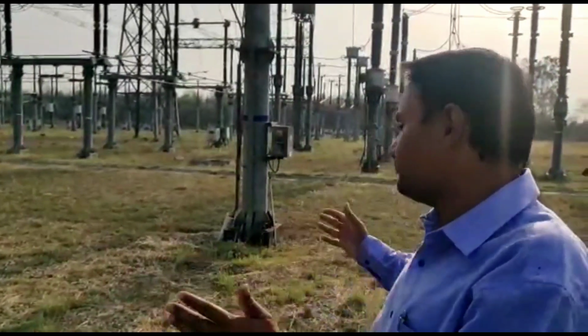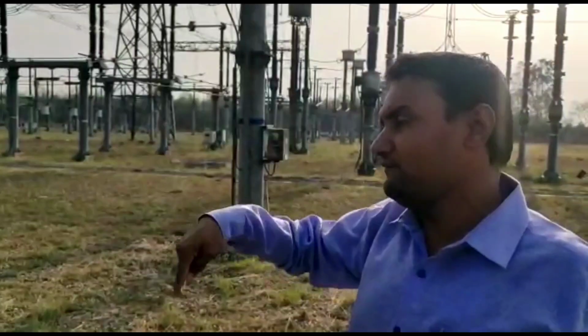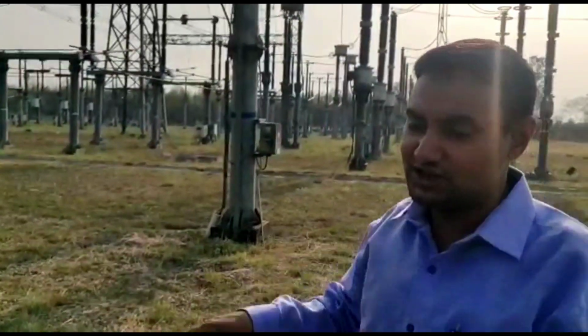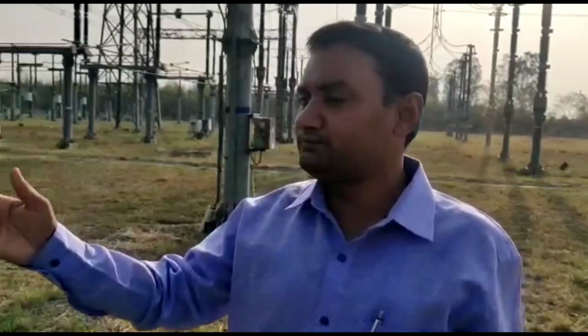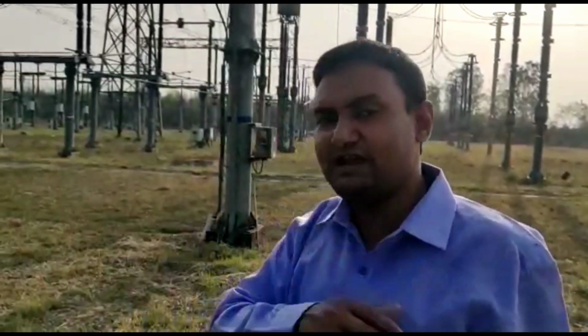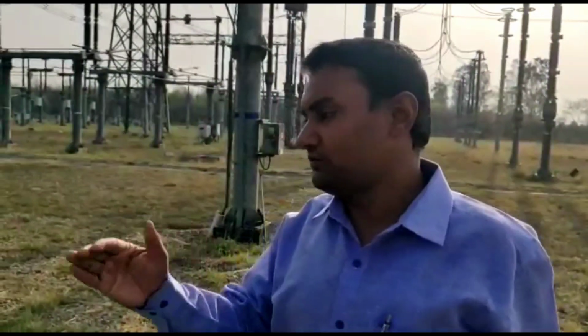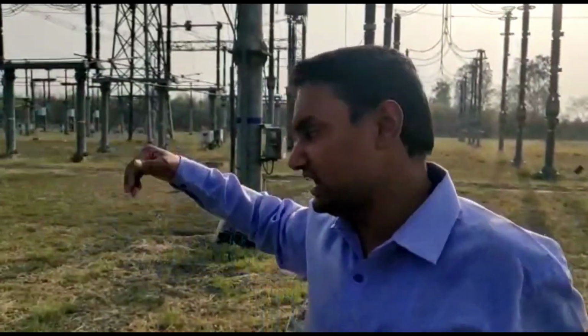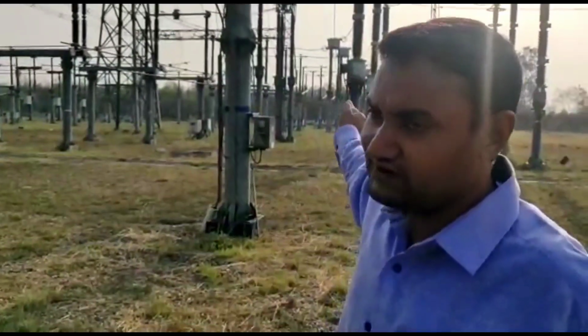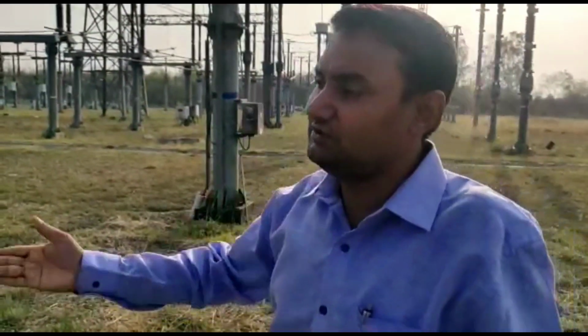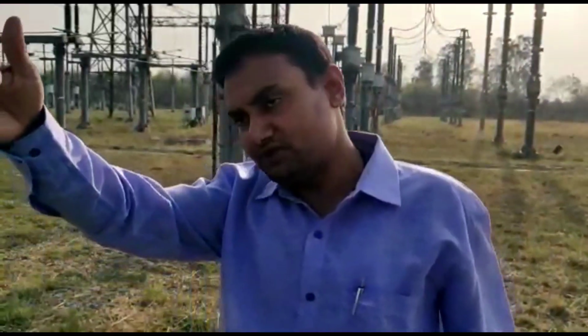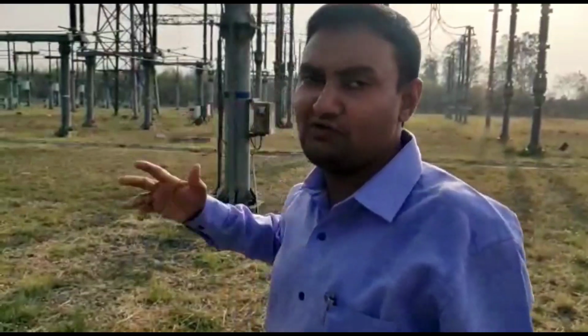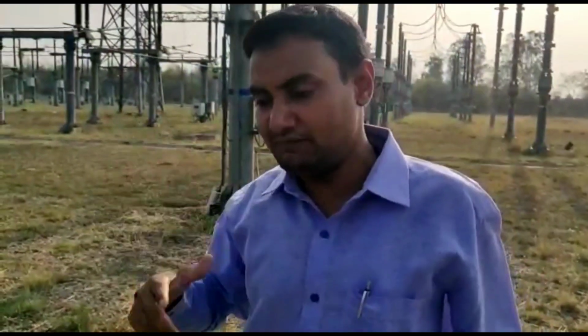So we are using phase to phase coupling. That means we are using LMU and wave trap in two different phases. And now if there is even a very severe ground fault in Y phase, the signal will still be transferred through R phase. If there is a fault in R phase, the signal will be transferred through Y phase. If there is a fault in B phase, then there is no issue, because both the R and Y phase LMU, PLCC and wave trap systems will be in healthy condition.